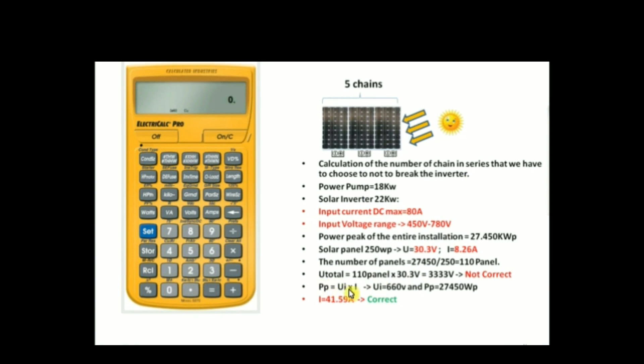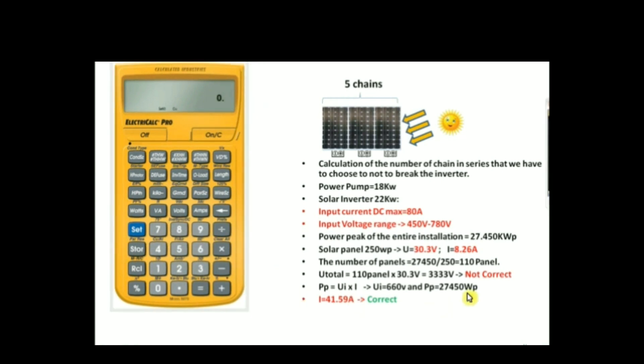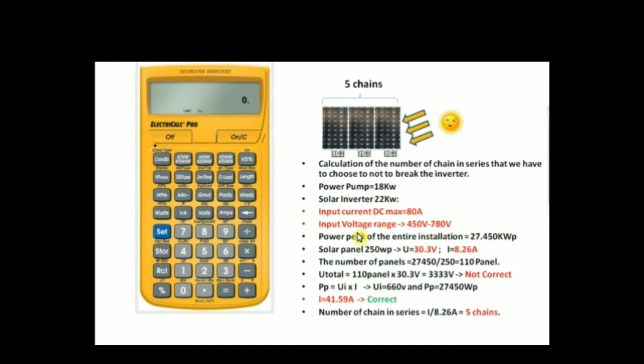We have the power peak of the installation. In one-phase mode, the power peak equals volts multiplied by current. We have already chosen the voltage to feed the inverter, which is 660 volts. We need to check that the resulting current is correct and does not exceed the inverter's input DC max of 80 amps.